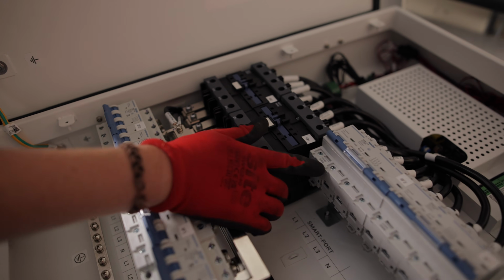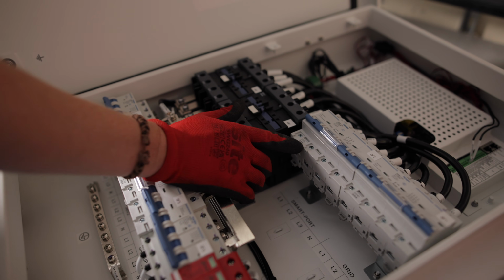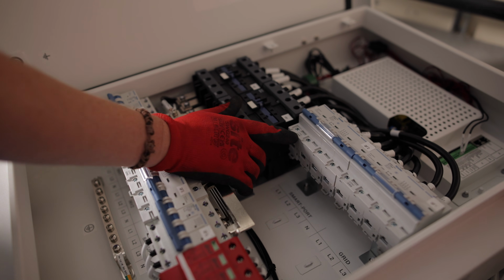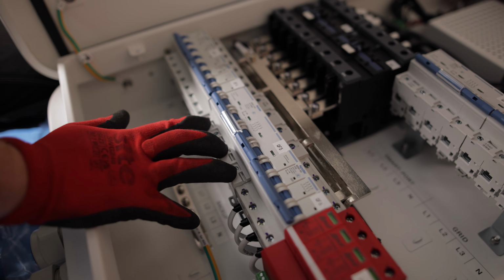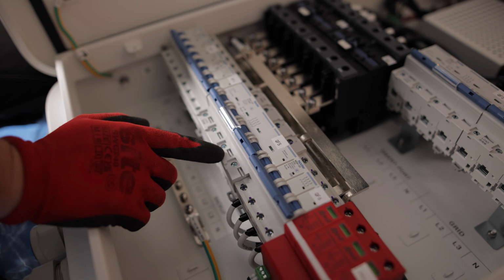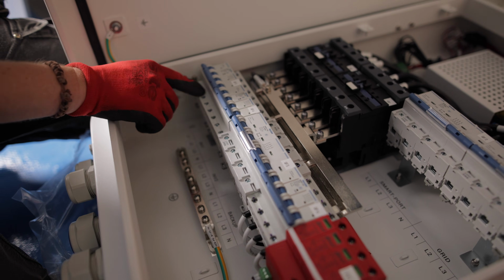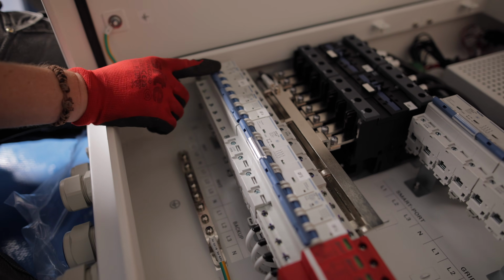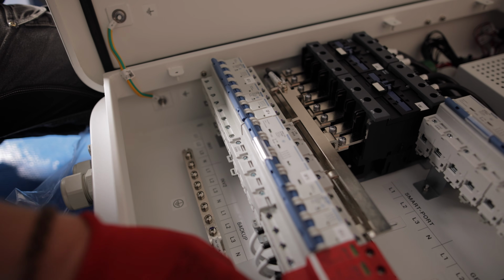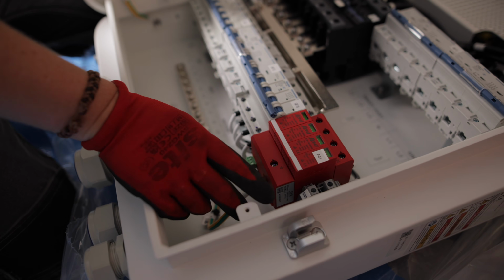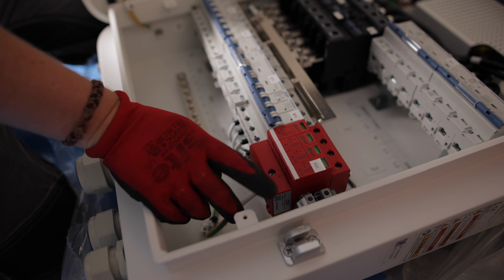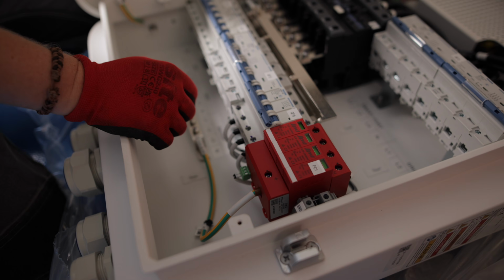The smart port is actually for if you want to connect like a diesel generator or something and you can have a second feed. The backup side is what's going to feed back out into our MCCB panel to run the whole property. We'll just use inverter 1, that's a 50 amp circuit breaker. And the nice thing is it's got a built-in AC surge protection device as well, and the inverter does have a DC surge protection device.